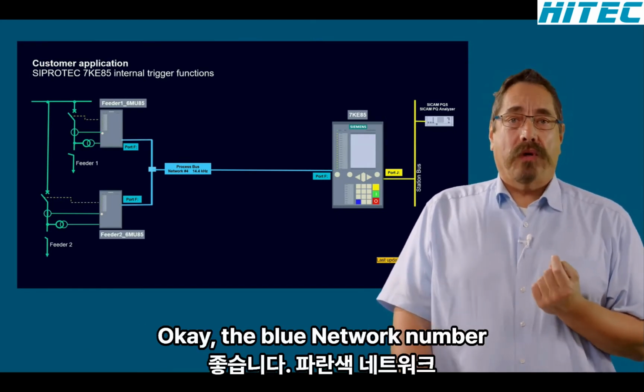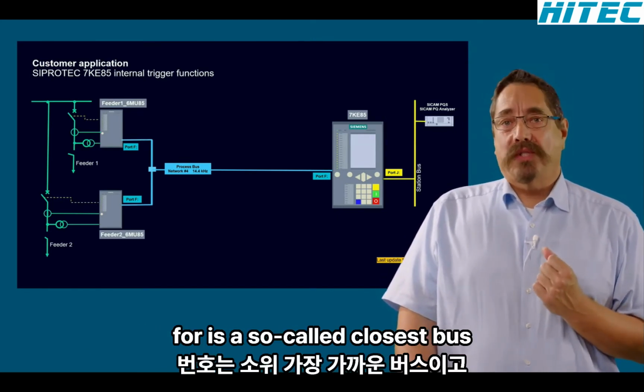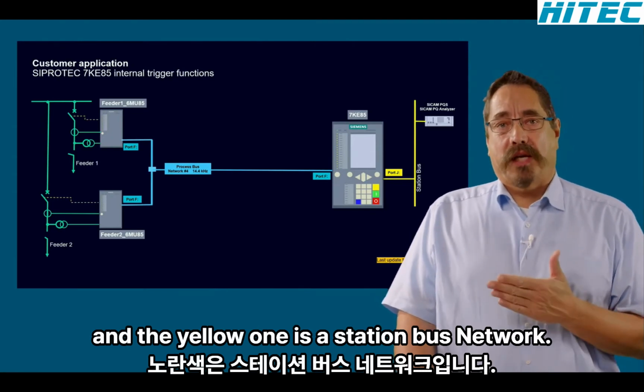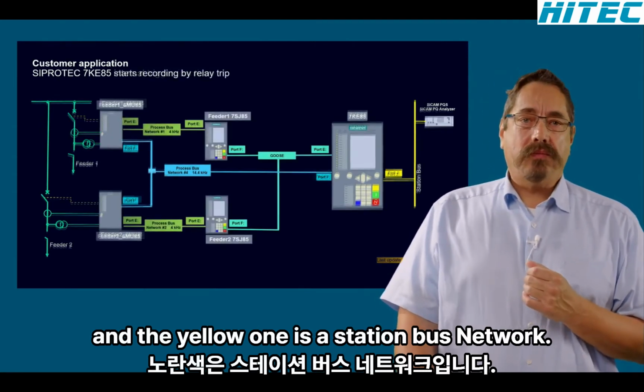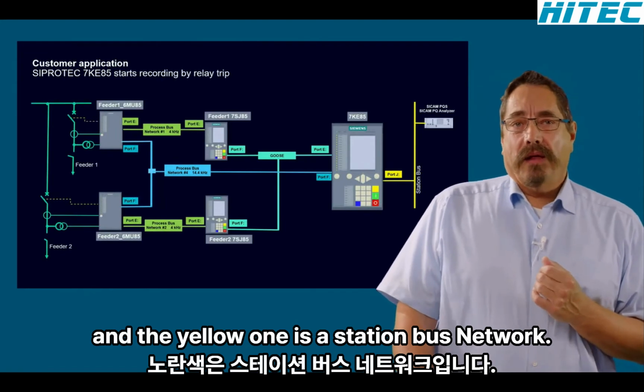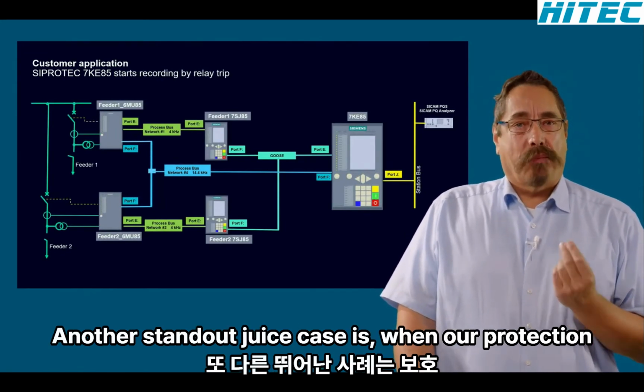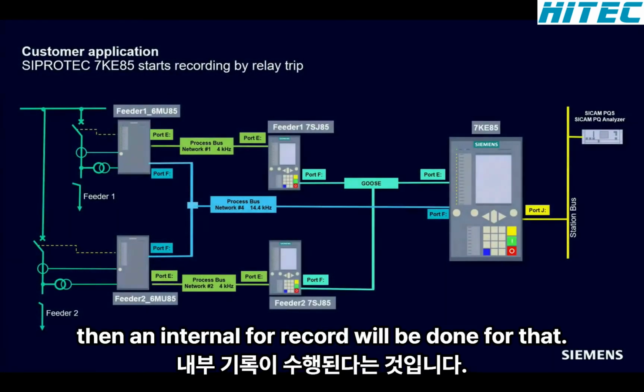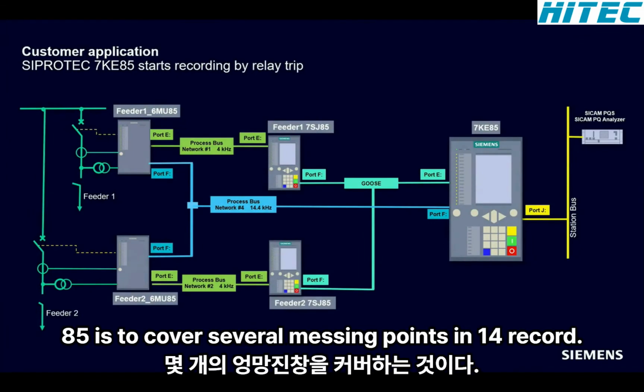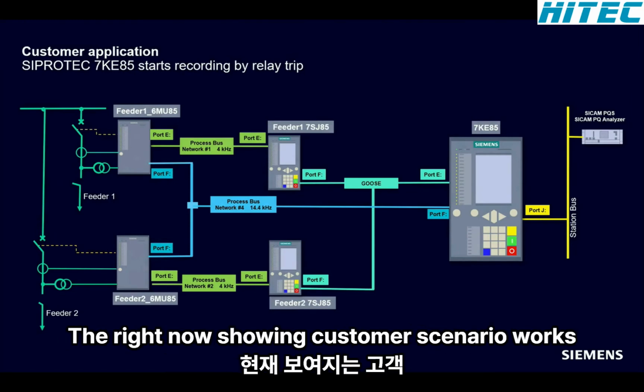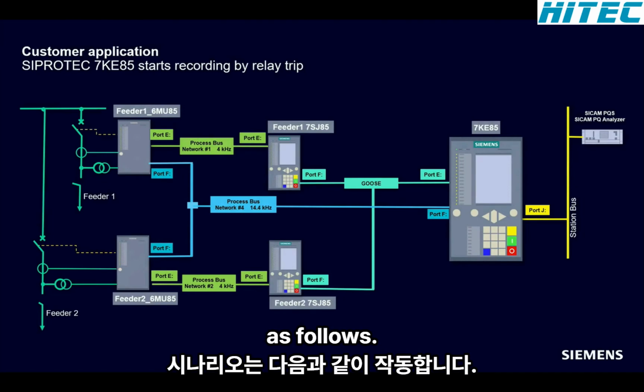Okay, the blue network number 4 is a so-called process bus, and the yellow one is a station bus network. Another standard use case is when a protection relay trips, then an internal fault record will be done for that single device. The benefit of the distributed fault recording with 7KE85 is to cover several measuring points in one fault record. The customer scenario shown right now works as follows.